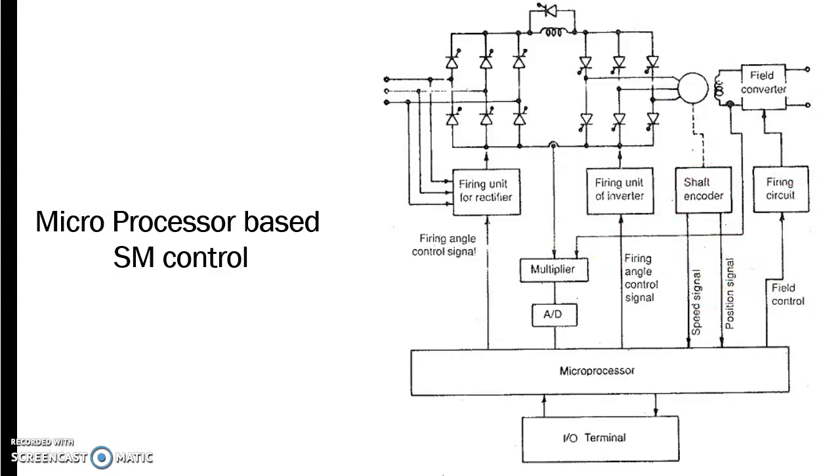The inverter triggering pulses are synchronized to rotor position reference signals with a delay angle determined by an 8-bit control input. The inverter SCRs are naturally commutated by the machine's voltage during normal conditions. The speed signals will be in digital form, a train of pulses of frequency proportional to the motor speed, and are fed to the programmable counter.